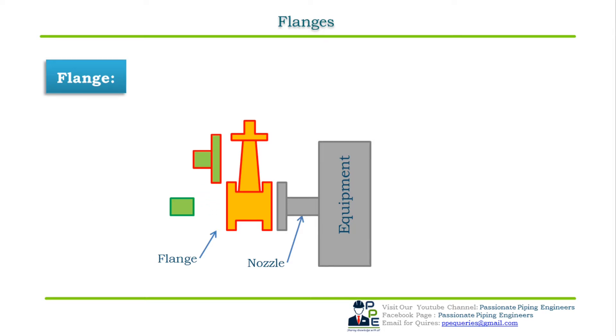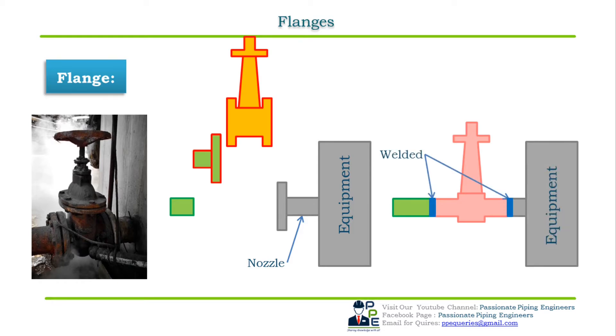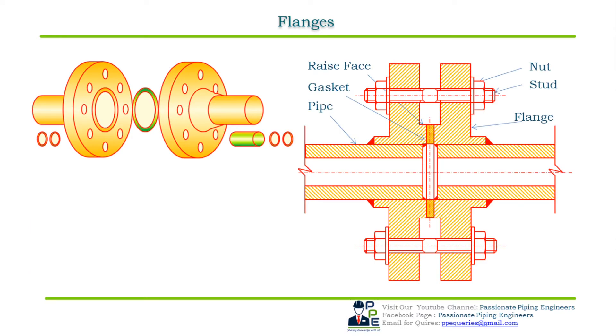Flanges are used as an alternative to welded connections to facilitate ease of shipping, erection, maintenance, and operations. If we weld pipes directly to valves, equipment, or other components which require maintenance, we have to cut the weld and modify it, which is not economical or good practice. Similarly, threaded connections cannot be preferred over flange connections in large bore pipes because threading a large bore pipe is not economical or reliable. Flanges are usually welded or screwed — socket welded, butt welded, or threaded — depending upon the size and requirements.